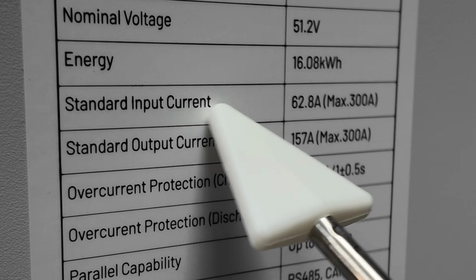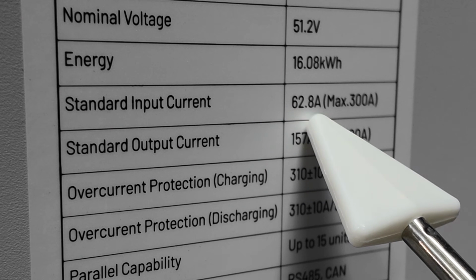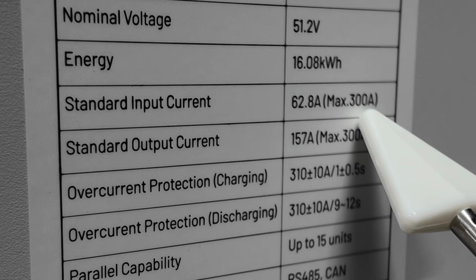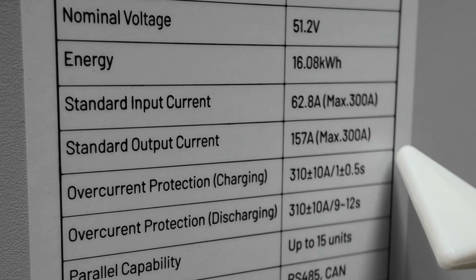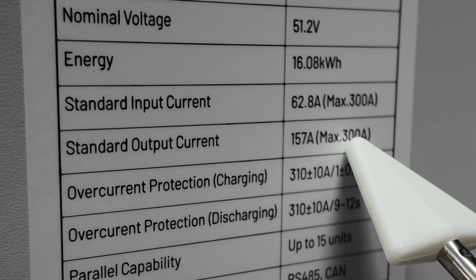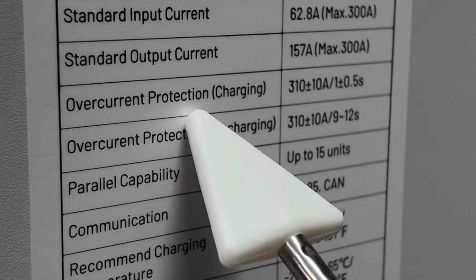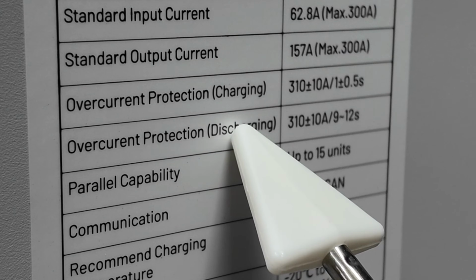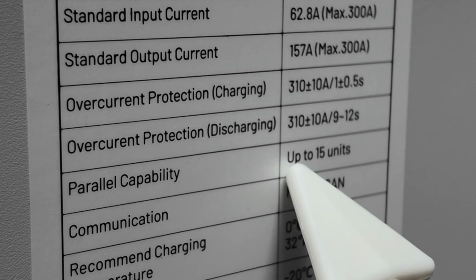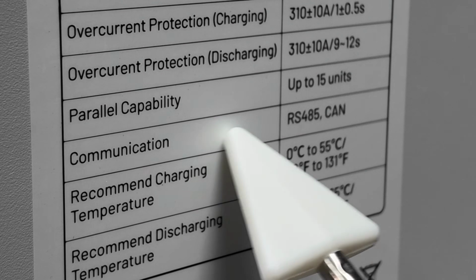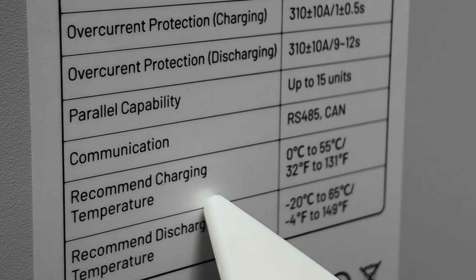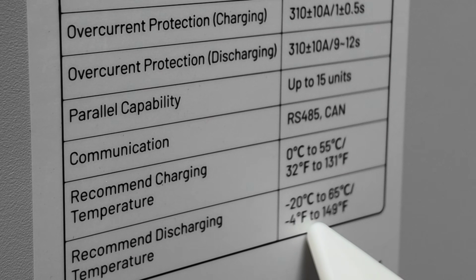Your standard input current is 62.8, but you can do a max of 300 amps, and as far as output goes, a max of 300 amps out. This also has overcurrent protection for charging and discharging, along with parallel capability of up to 15 units. And then your communications and your recommended charging and discharging temperatures.